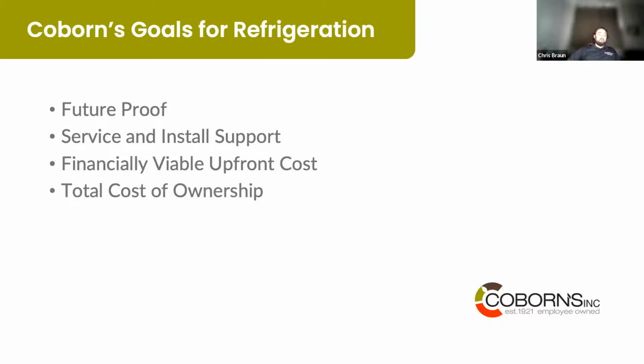Our goals for refrigeration, when we were contemplating between using synthetic refrigerant and natural refrigerant, were to be future proof. We wanted to make sure that when we were spending the capital to do a new store or remodel, we were setting ourselves up for the next 20 plus years, and that we weren't going to put something in and have it be regulated out in the next 5 to 10 years. We also wanted good service and install support, to make sure we have contractors in the area that could support the technology and get it installed cost-effectively. And it needed to be financially viable upfront, and justifiable with the total cost of ownership over the lifespan of the equipment.